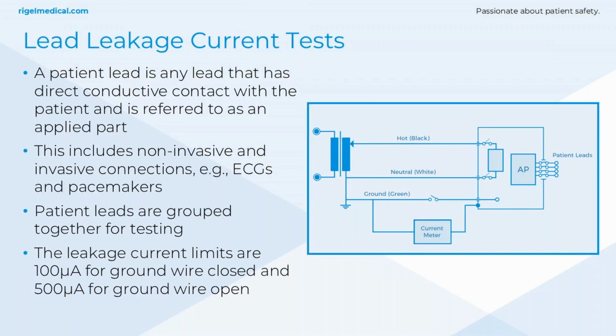NFPA 99 originally said that each individual applied part to ground must be measured. However, in the last few editions of NFPA, including 2021 and 2024, patient leads are grouped together for testing. So testing should be carried out using the suggested circuit in the image with the device powered on. The leakage current limits are 100 microamps for the ground wire closed and 500 microamps for the ground wire open. So you're taking two tests for patient lead leakage.